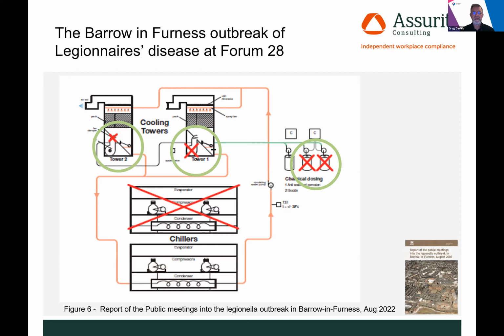Cooling tower number 1: the impeller blades on the fans drawing air in to help cool the water within the system were so badly corroded that many of them were actually found sitting in the bottom of the tower's pond. As a result, with both towers operating very ineffectively, one of the chillers had fallen over, so it was only operating off one chiller.